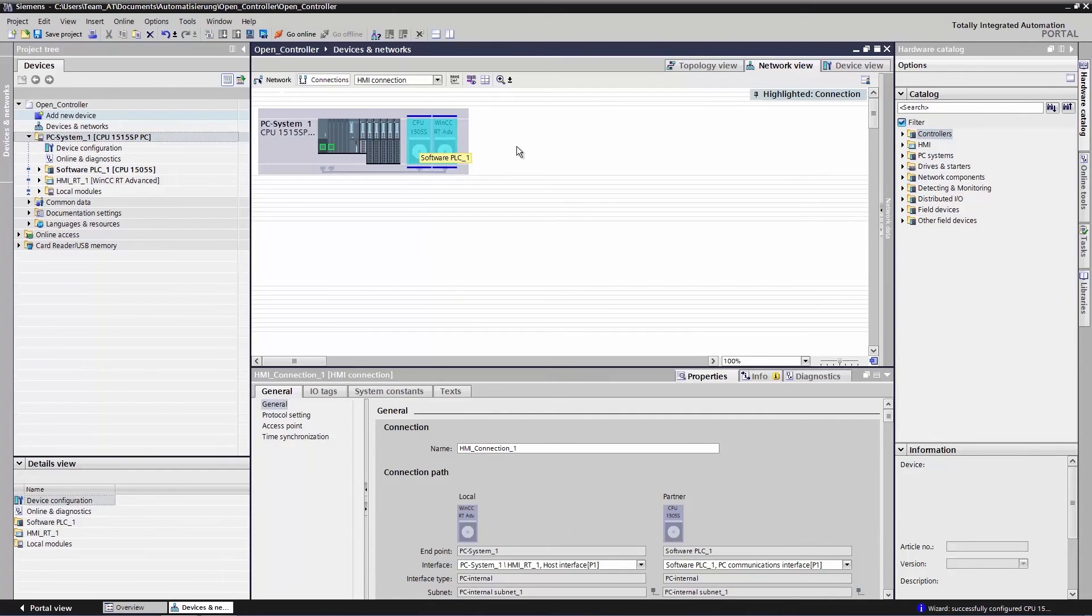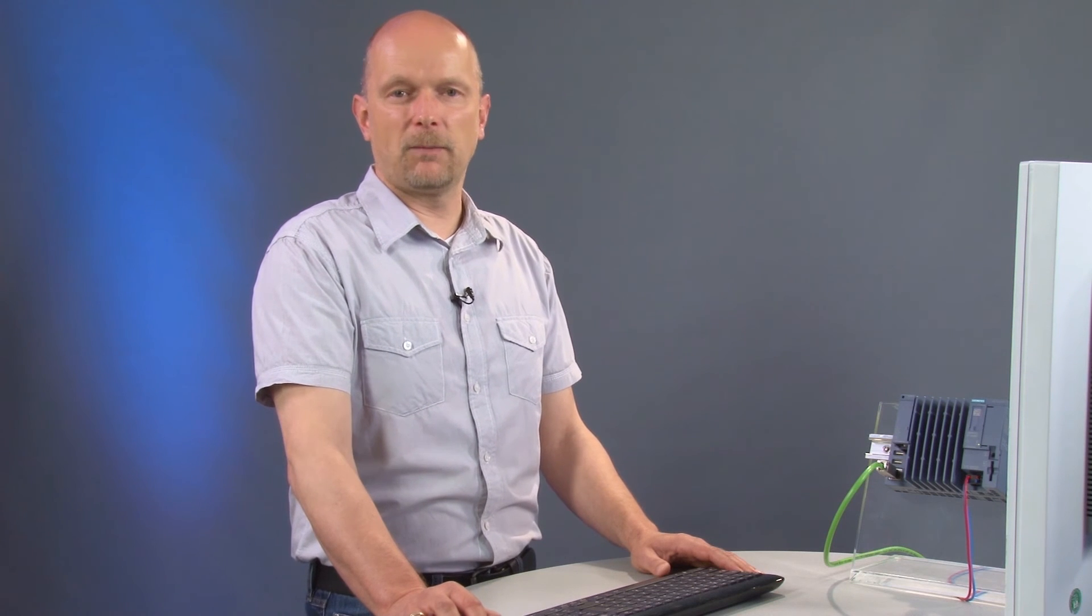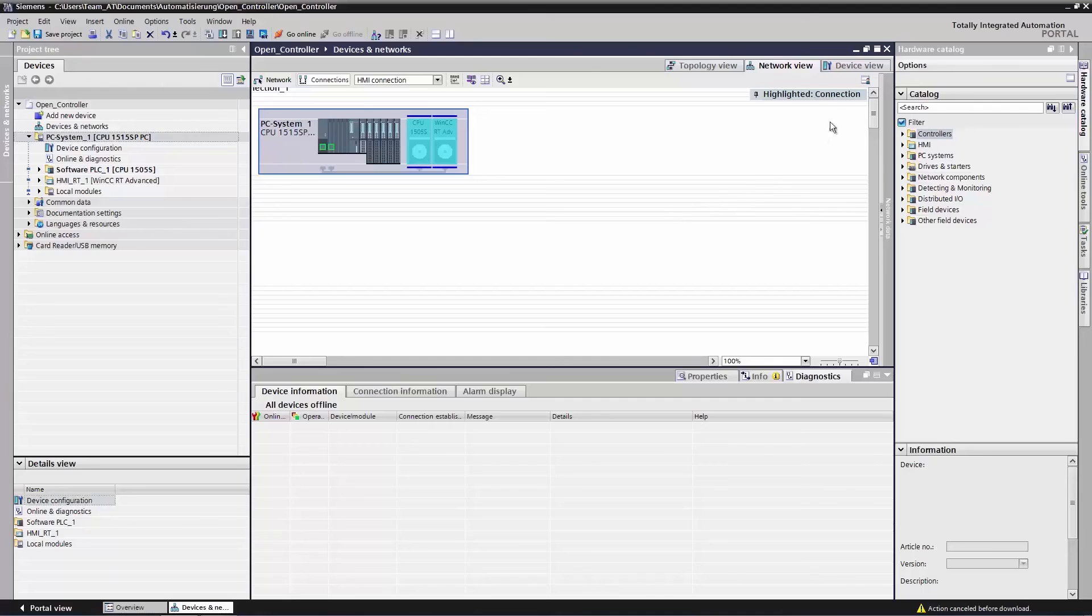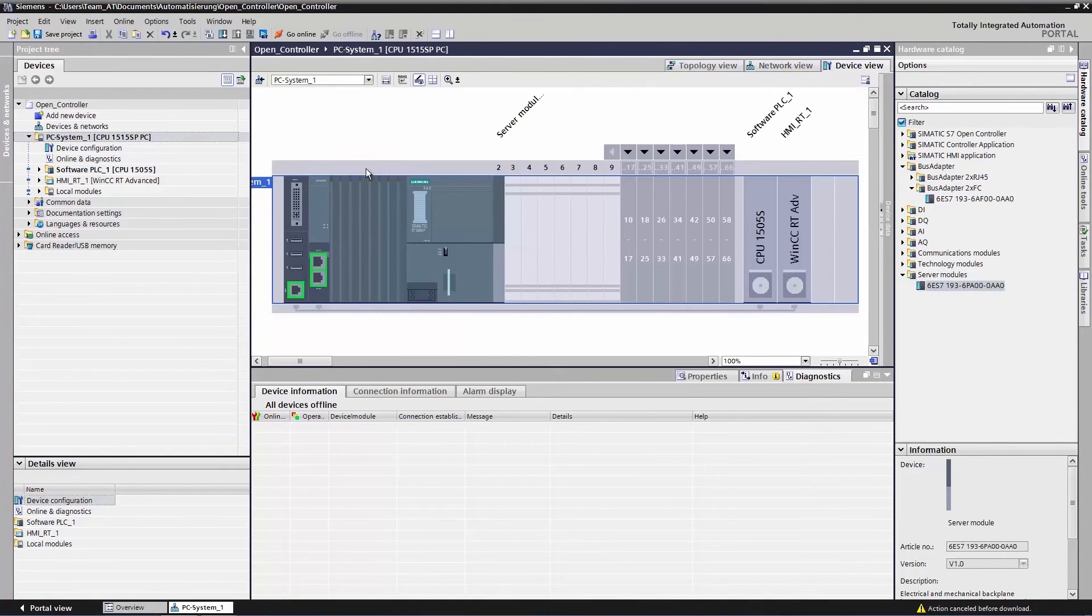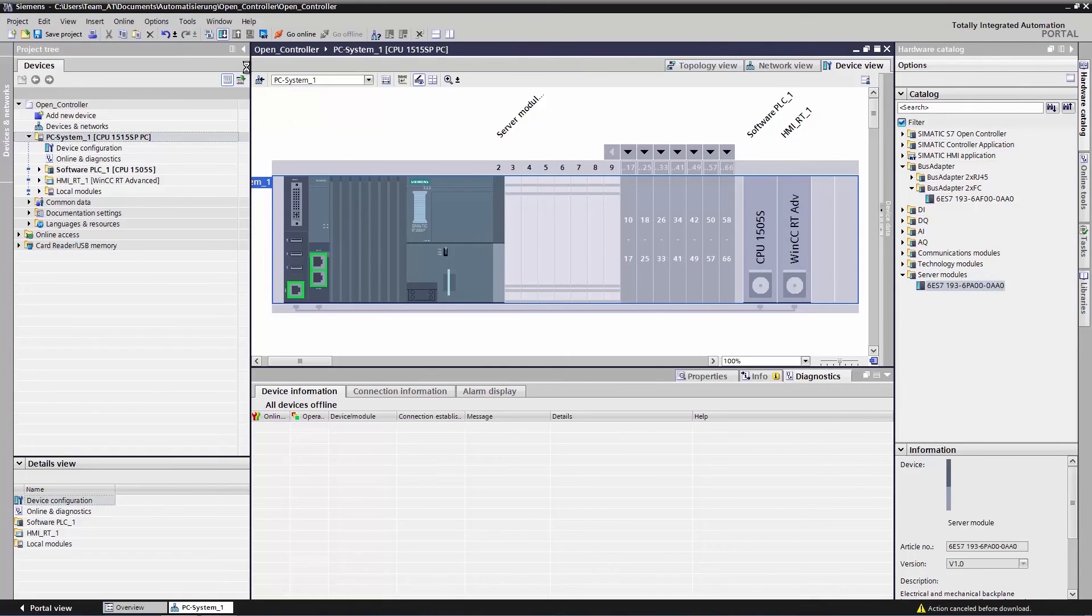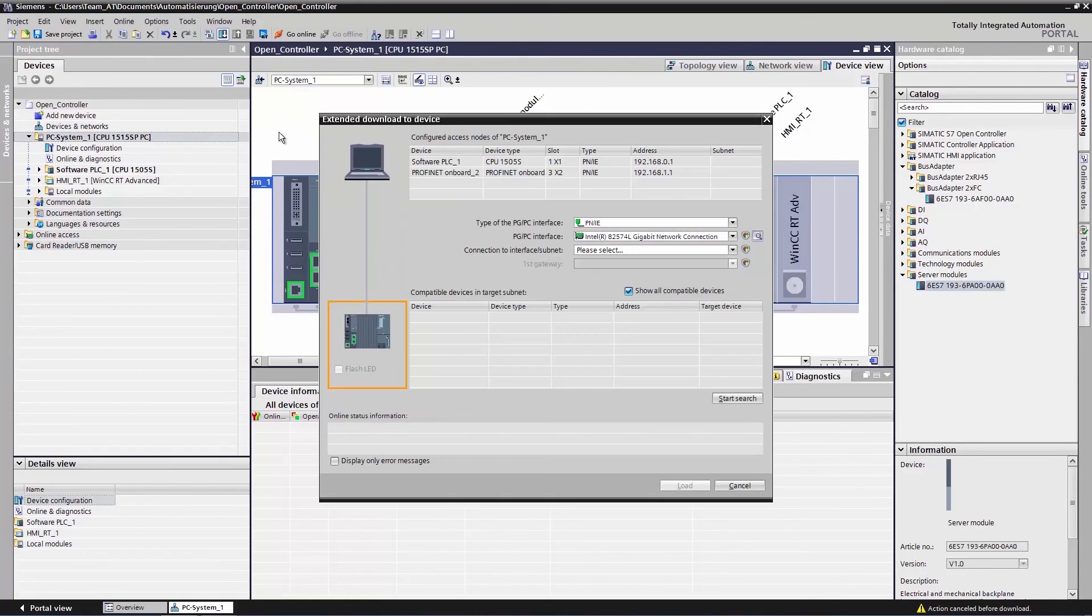Our configuration is now complete and we can load our project for the first time. Please note that you will only be able to load the complete PC station when loading the configuration for the first time and that you will need to use the X2 interface to do so. We will now change over to the device view once more and click to select the PC station. We now select the download button in the function bar.